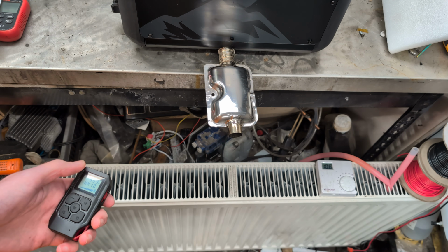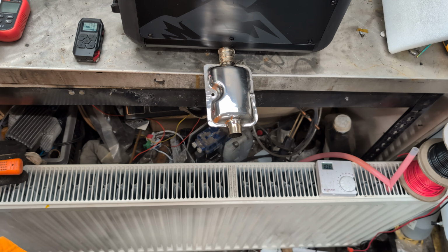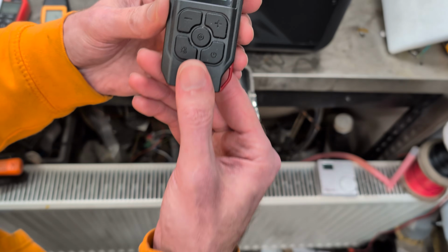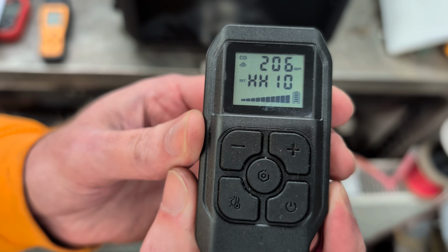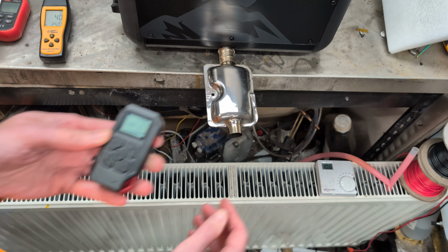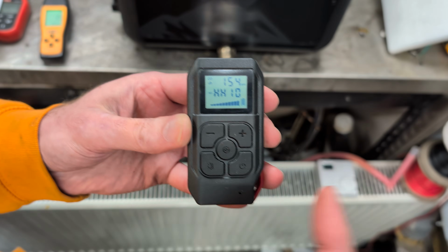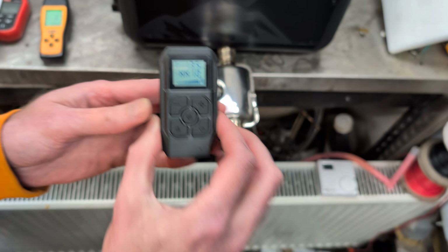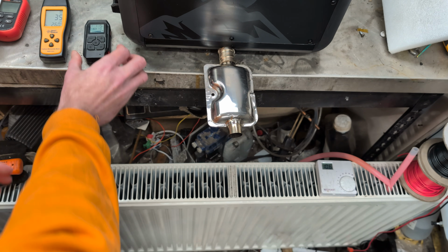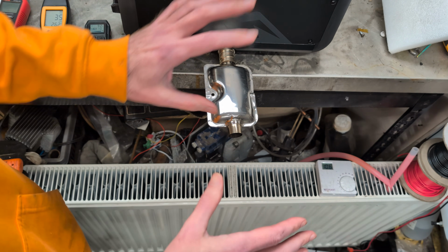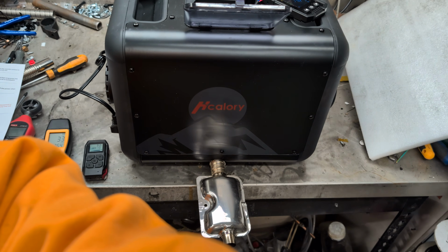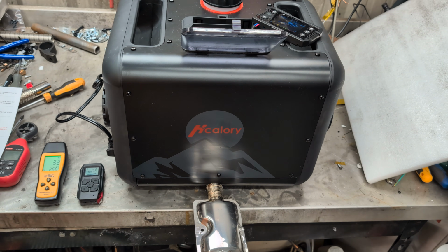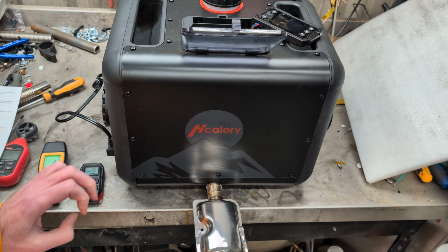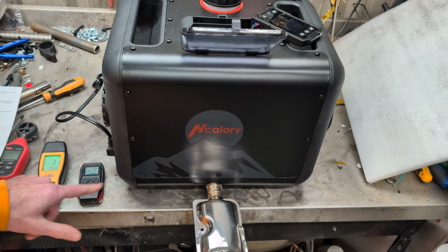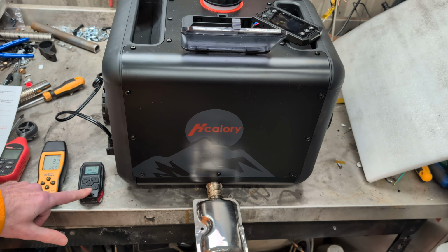Oh man, that exhaust is hot. I think I might have actually detuned mine too much. Well, it did the thing, it showed me what the carbon monoxide was like. So it does work - it gives a carbon monoxide reading, and it will turn the heater off if it sustains a terrible carbon monoxide reading. You can adjust it in the app on the phone, bringing it down to trigger at a different level. But it does work, it's reading carbon monoxide in here. Thank goodness - I'd obviously had it too well tuned previously, so I adjusted the tuning on the controller, made it worse, and now it detects the carbon monoxide levels in here. Good, so that works - it does cut out, and it did cut out previously when it was overreading.